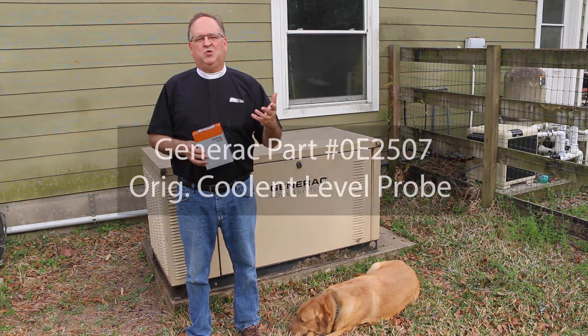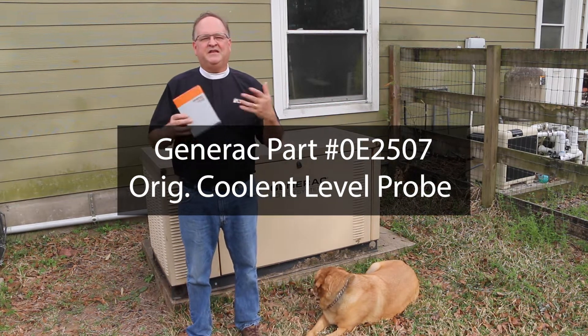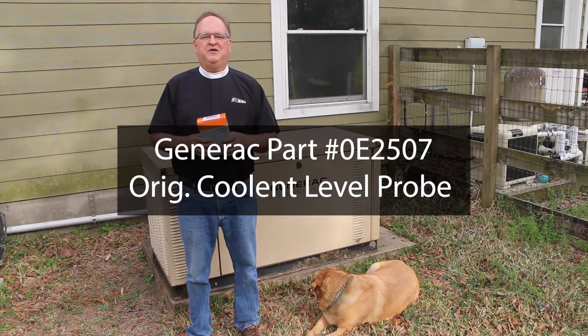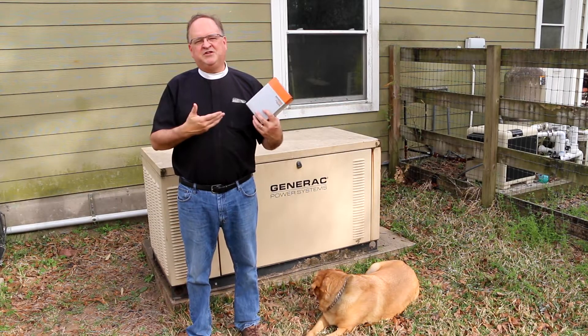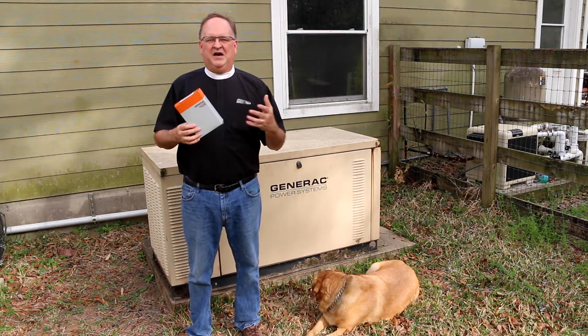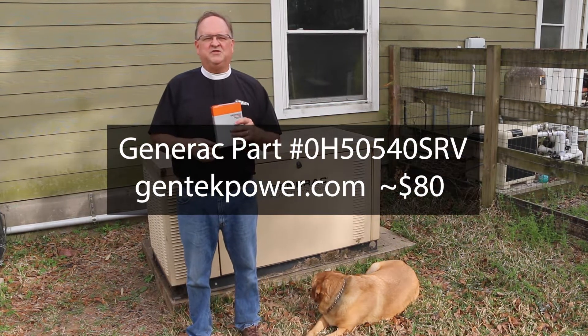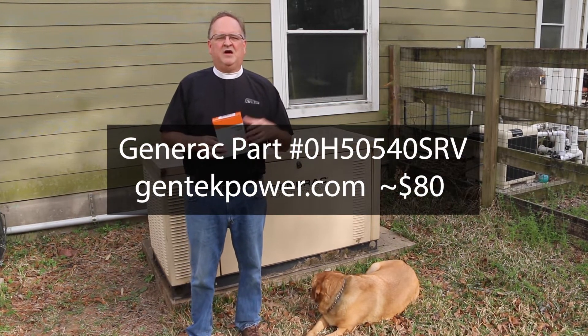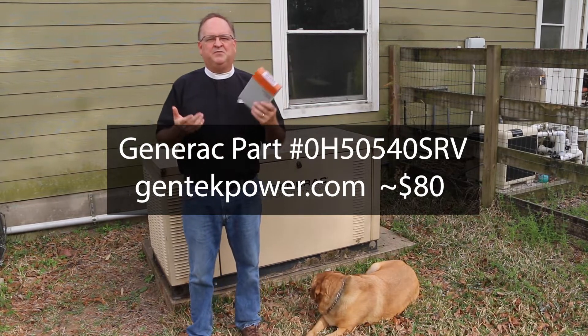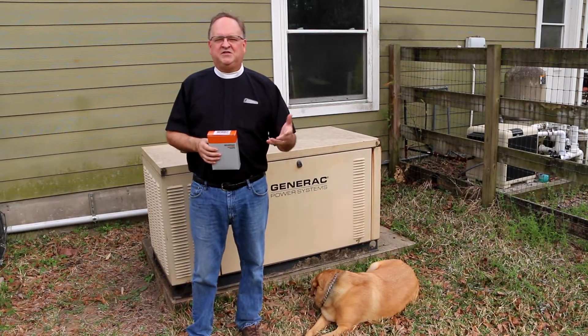So if your generator has coolant probe part number 0E2507, it needs to be replaced with a new probe and a sensor interface module. There are different kits depending on what controller your generator has. For R200 controllers like mine and above, you need Generac part number 0H50540SRV. I bought this kit from gentekpower.com for less than a hundred bucks, but if you have a panel other than an R series, you'll need a different kit.